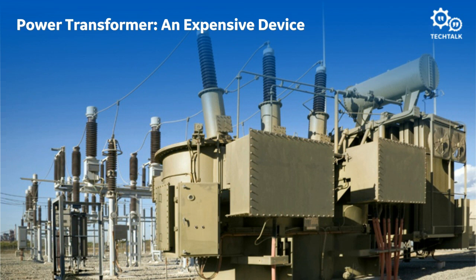If any of you have ever witnessed a transformer failure or seen any of the videos circulating online, you know that it typically is not a case of the transformer just stops working. It could potentially be a catastrophic failure if a fault is left uncleared or not cleared fast enough. Because most transformers are oil filled, an explosion is a very real risk, and at that point, it's a risk to the other equipment around it, and more importantly, to any people around it. So proper protection is important.